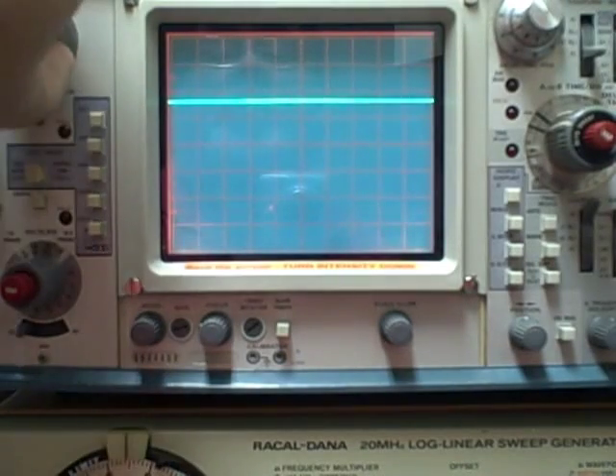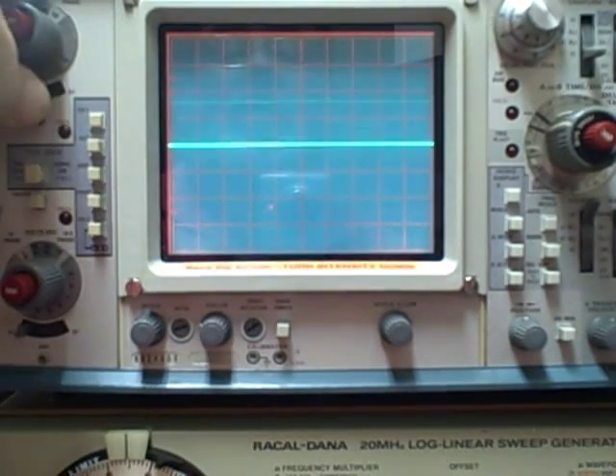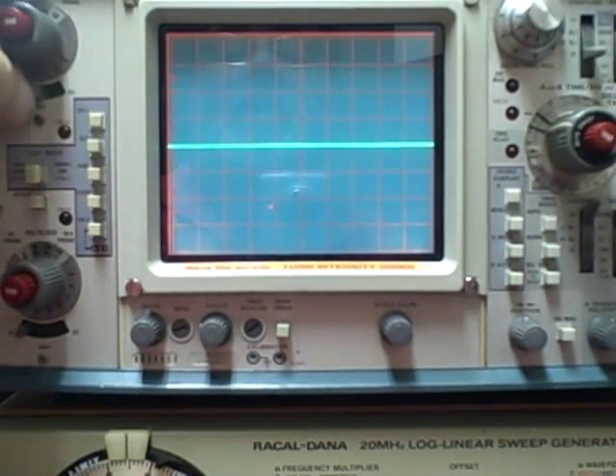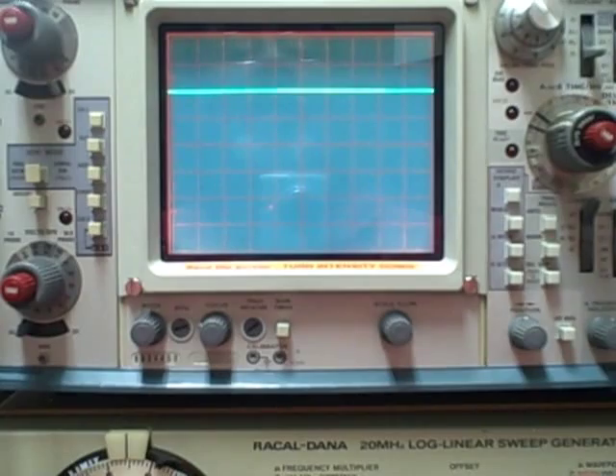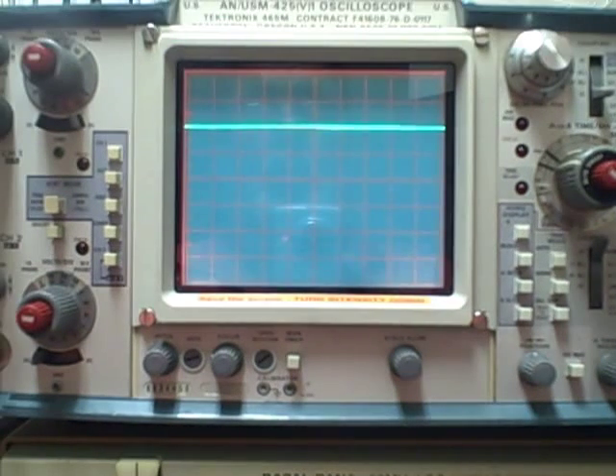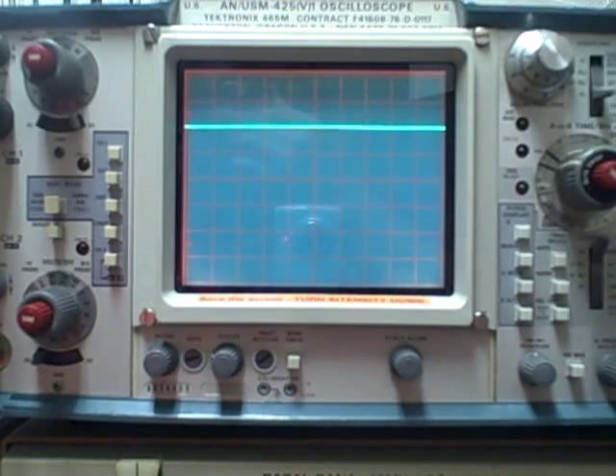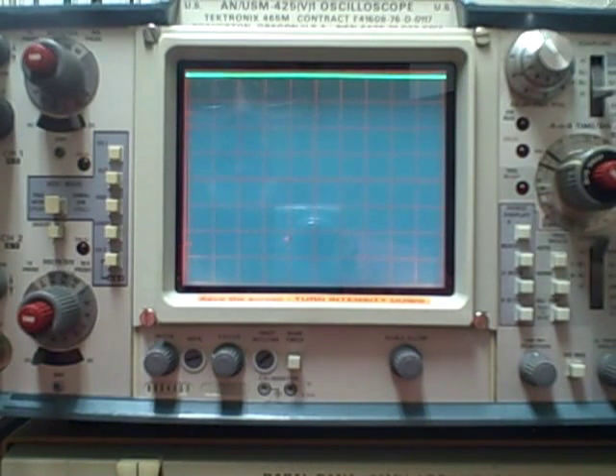We're right now on 5 volts per division. If we want to be 2 divisions above the half mark, that would be 10 volts. Here's 9, there's 10, 2 divisions up, 5 volts. We're at 10 volts coming in, 5 volts per division, up 2 divisions, that's 10 volts. If we go to 20 volts coming in, we're full scale, since 4 times 5 is 20. So for DC, we are right on the money. It's perfectly calibrated.